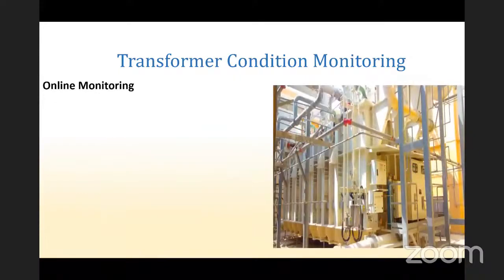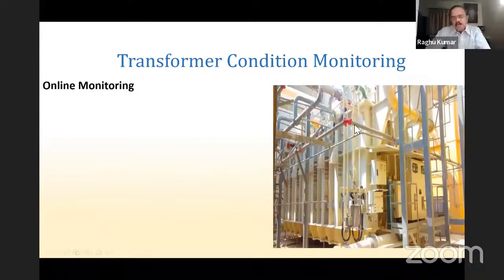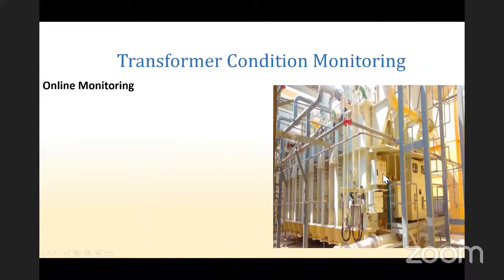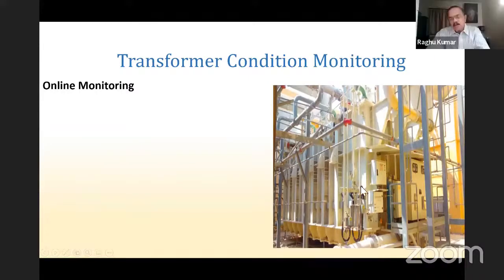Next comes online monitoring. This is an 800 MVA transformer where you can physically see certain things. This is the online monitoring device, and this is a monitoring system where all the data from all other sources comes here for monitoring. This information is taken inside the control room to an HMI, and that HMI has the software for all the analysis purposes.